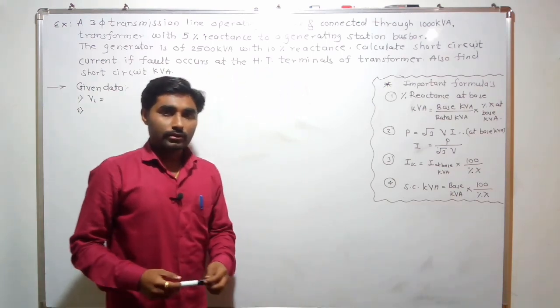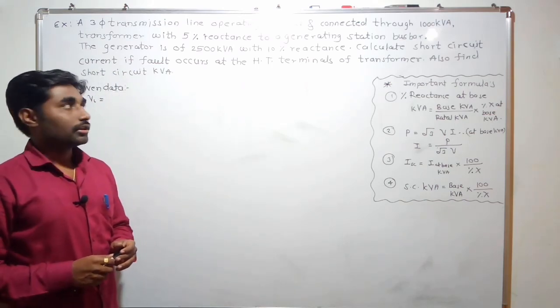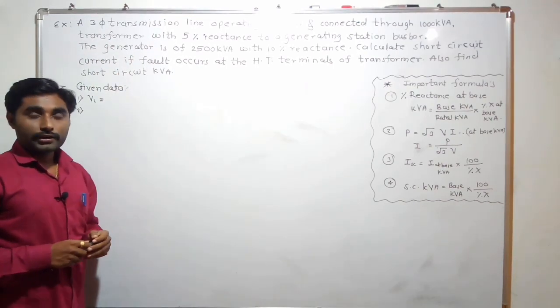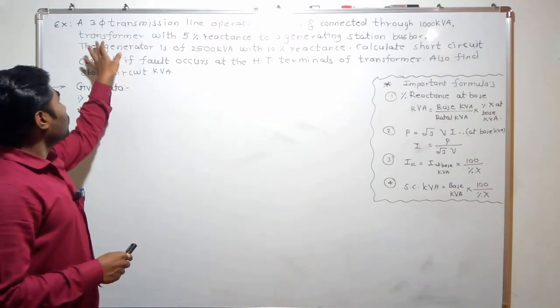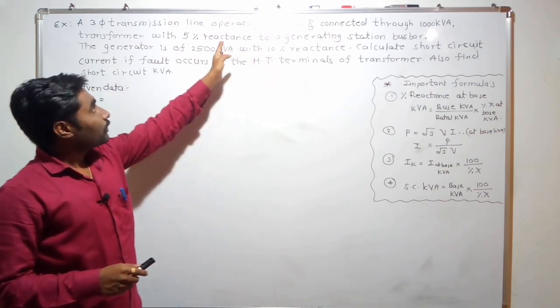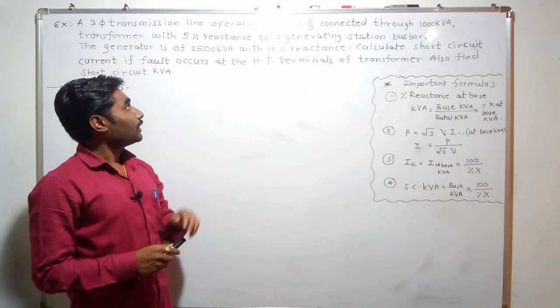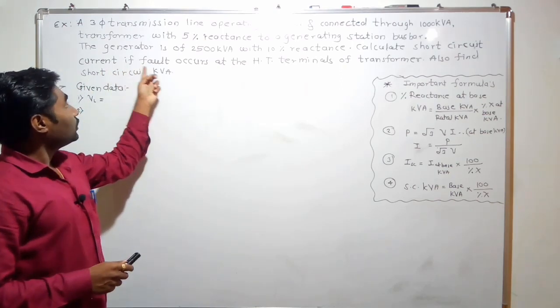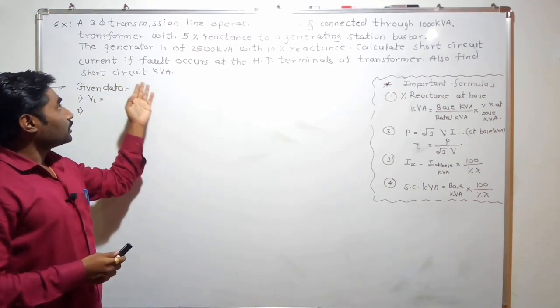Here I have written one example, so let's first read this example and then we will solve it. A three phase transmission line operating at 66 kV and connected through a 1000 kVA transformer with 5% reactance to a generating station bus bar. The generator is of 2500 kVA with 10% reactance. We have to calculate short circuit current if fault occurs at HT terminals of transformer, and also we have to find out the short circuit kVA.